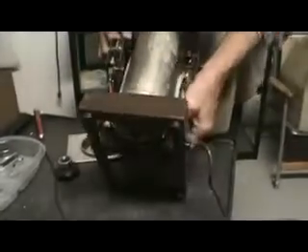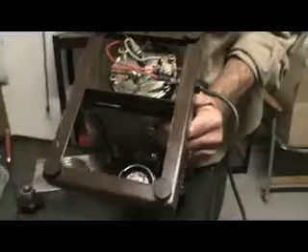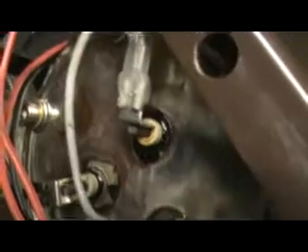But the other thing we're going to notice here is that every electrical connector but one is melted or gone. These are melted off. You see, these are just completely gone. Now it's like that white wire, the insulation is broken on it at that connector. Oh yeah, back in here. That looks dangerous. Yeah, right there.